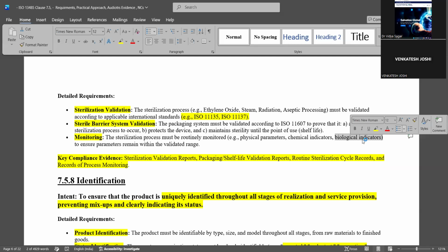If the microorganisms in the vial are not killed, then you keep it in the incubator. The incubator provides a conducive environment and temperature for growth. When you keep it in the incubator and they start growing, it means the sterilization didn't happen properly, because the organisms are still alive. If they are dead, they won't grow. If they are not dead, they start growing and the media will become turbid. If they don't grow, the media will be clear. So that is how you use biological indicators.